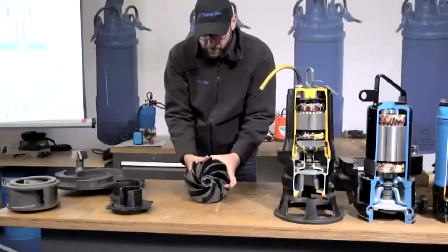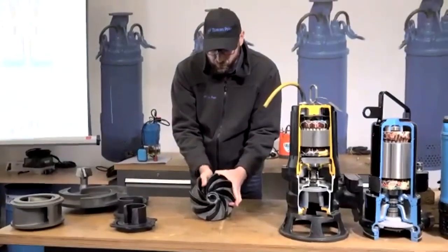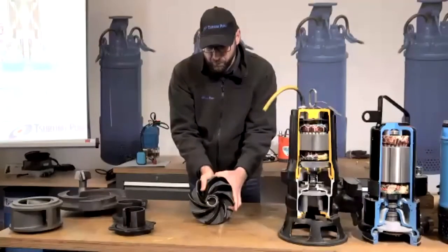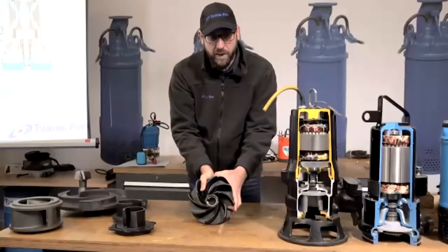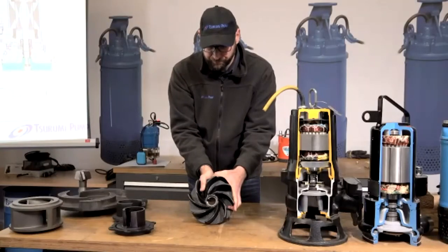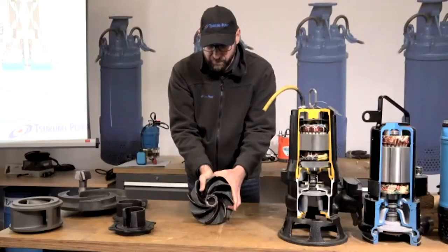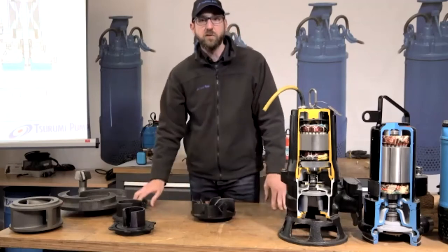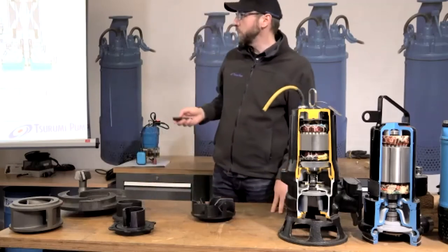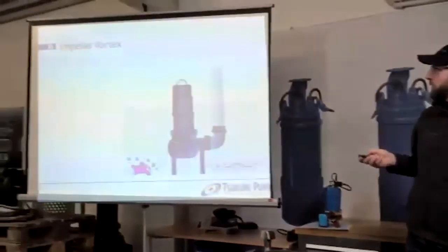The vortex impeller, due to the vortex effect, is not in direct contact with the medium. This is an important point when we talk about the recommended medium for this type of impeller. It has a direct effect on abrasion resistance: the less direct contact between an abrasive medium and the impeller vanes, the less abrasion you will have.